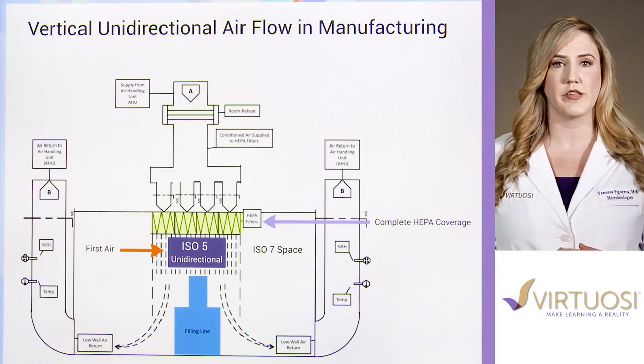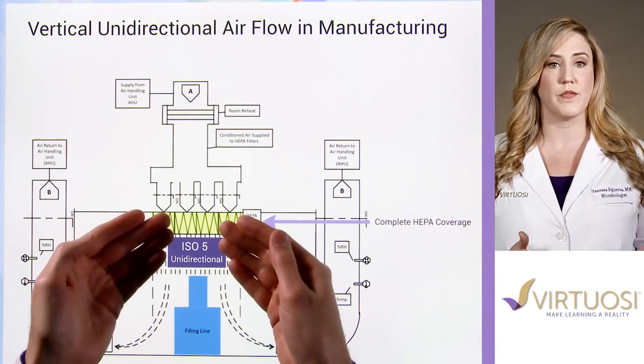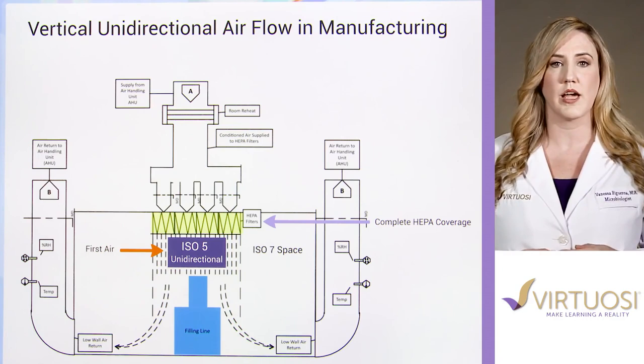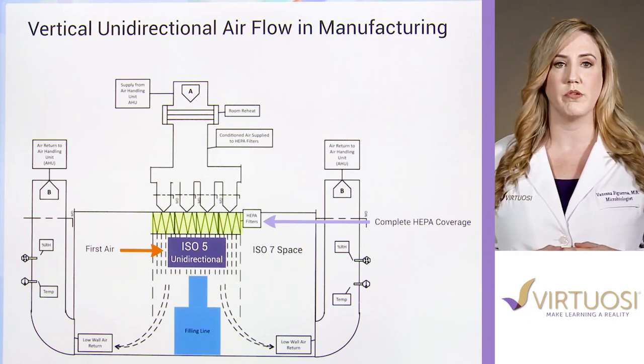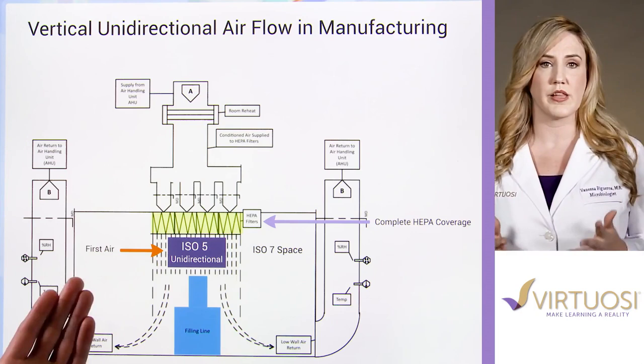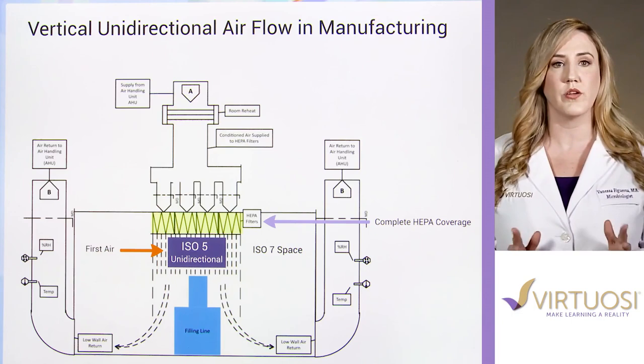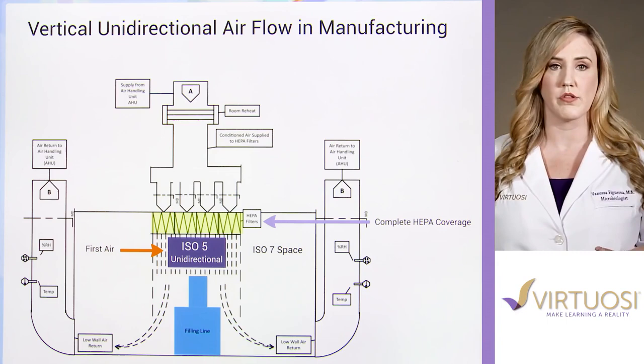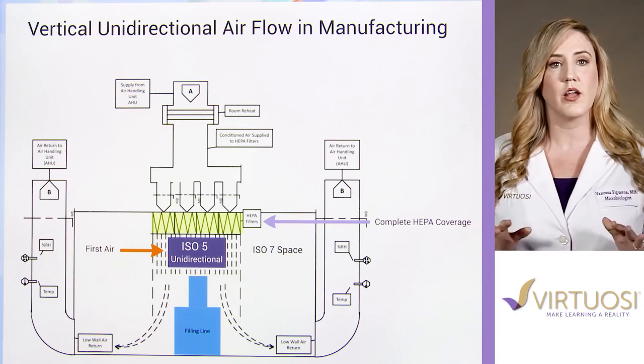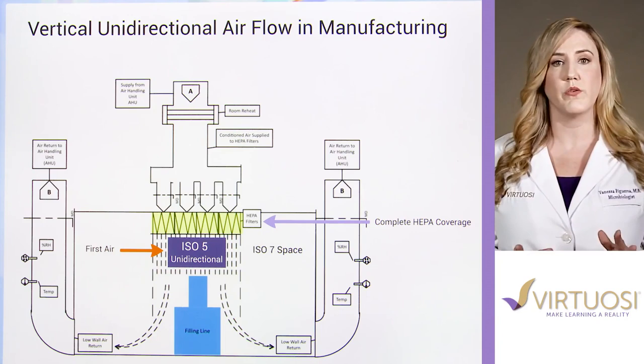Unidirectional airflow is used in critical areas such as ISO 5 or in laboratory testing hoods where the first air that comes into contact with open product, open containers, container closures, or product samples is required to be of the highest purity possible. The principle of first air is one of the most basic principles in aseptic technique. This principle states that humans interacting in the environment should never disrupt the unidirectional airflow over open containers, product contact components, or samples.